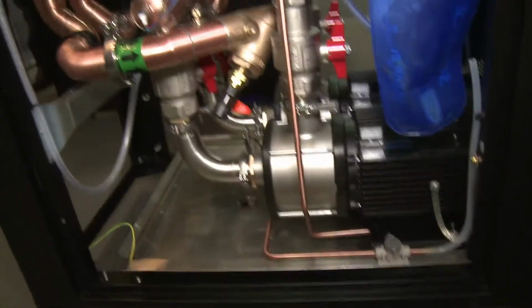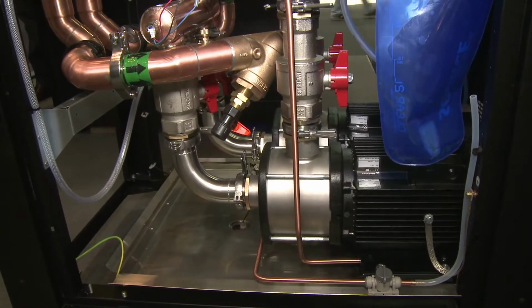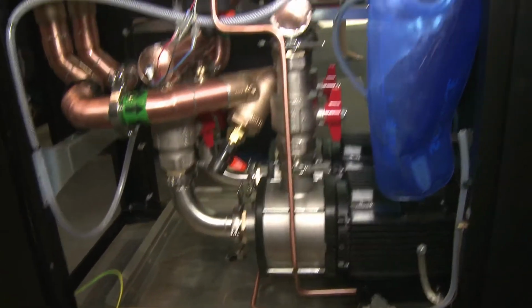Obviously, you see there we've got dual redundant pumping capabilities. Each pump does between 360 to 380 liters per minute, and there's a fairly sophisticated control system built in, such that every week you use one pump. It'll then switch over to the other, so that their service life is the same, and you're guaranteed that you're not going to have the backup pump be dried out or potentially not working, and that be a surprise when you need it the most.